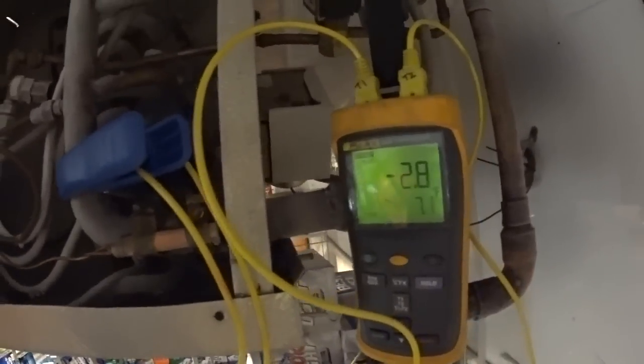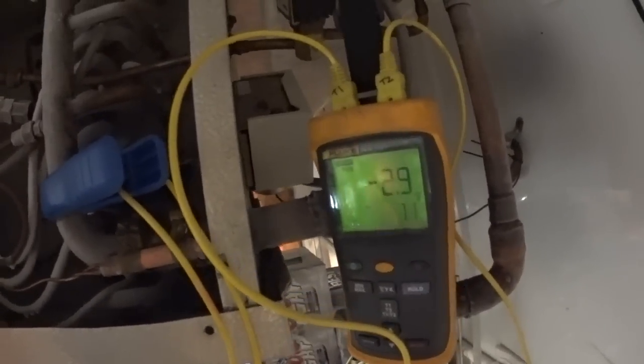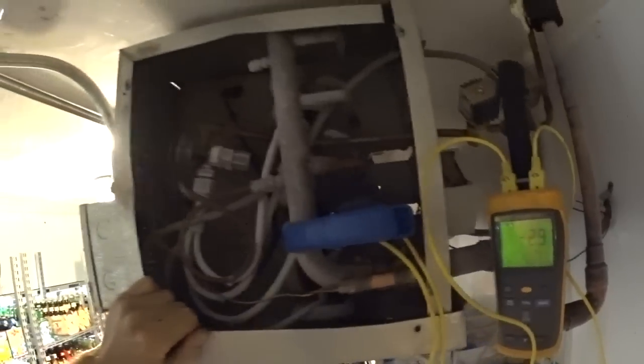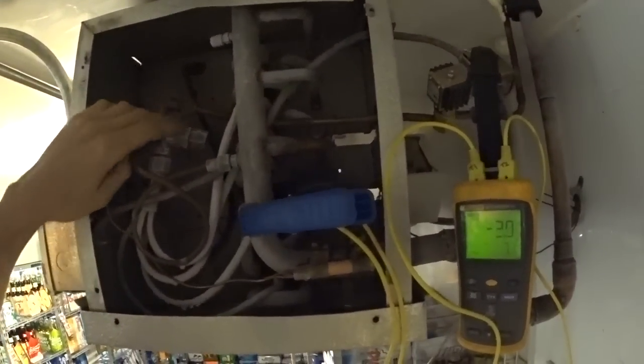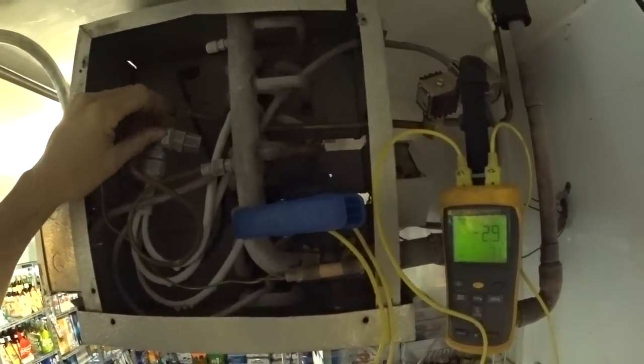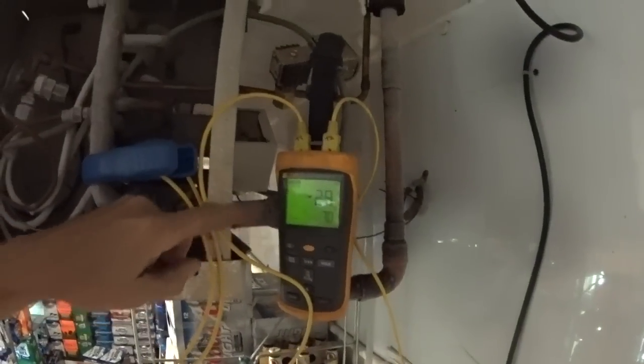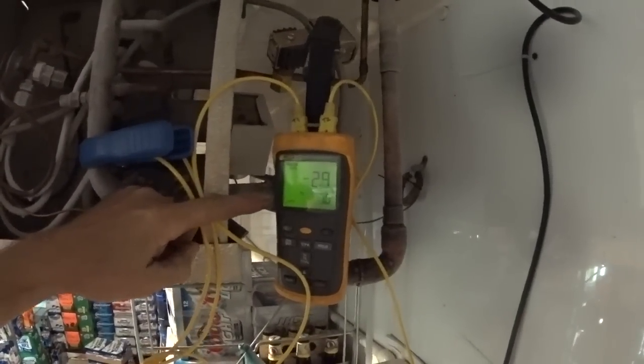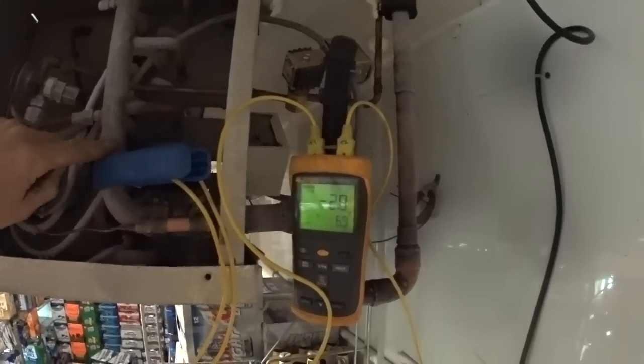And this expansion valve is doing what's called hunting, and it'll open the expansion valve here, it'll open up and let a lot of refrigerant through it, and my temperature difference will go down, a little way too cold.